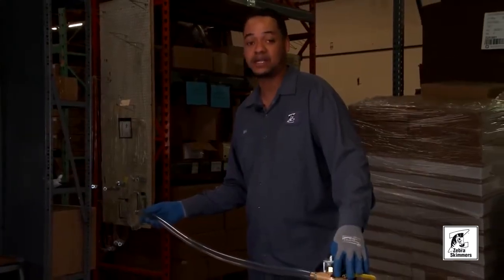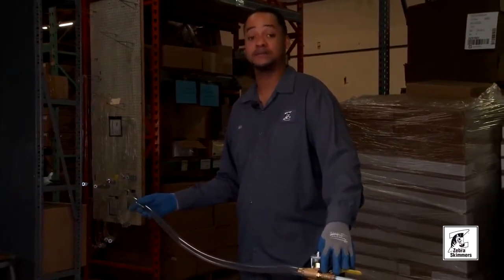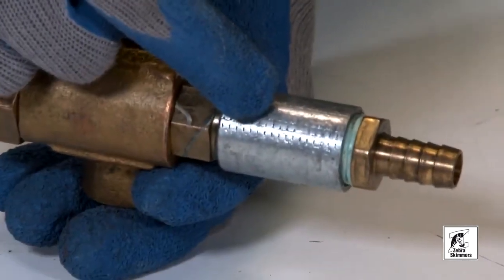Even in the downward motion, you must use the hose length we give you. If you extend it, you're not going to get the back pressure or the output needed — it will not work. We do not recommend switching our fittings.